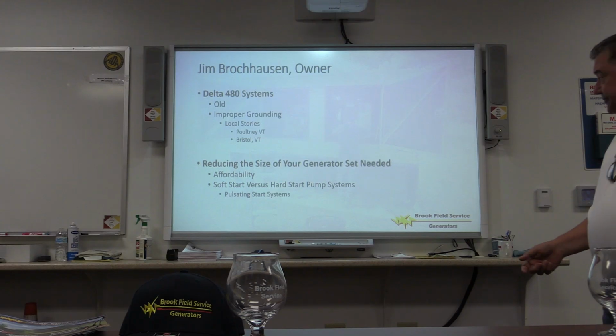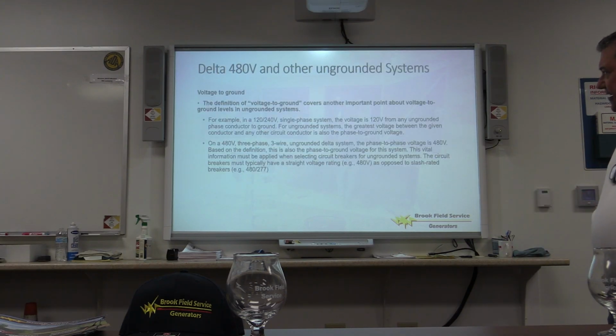Go to the next slide. This is a definition of voltage to ground, which is an important issue. For example, on a single phase system, the voltage is 120 volts from an ungrounded phase conductor to ground. For ungrounded systems, the greatest voltage between the given conductor and other circuit conductors is also phase to ground. On a 480 three-phase, three-wire ungrounded delta system, the phase-to-phase voltage is 480 volts. Based on the definition, this is also the phase-to-ground voltage for this system. This vital information must be applied when selecting circuit breakers for ungrounded systems.